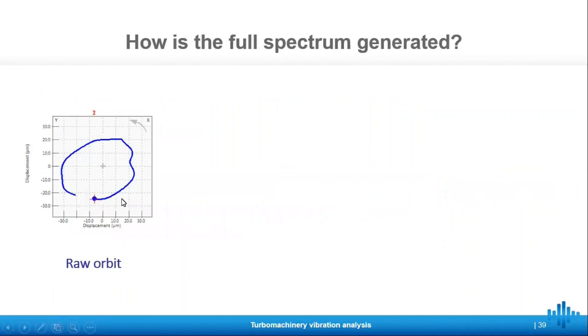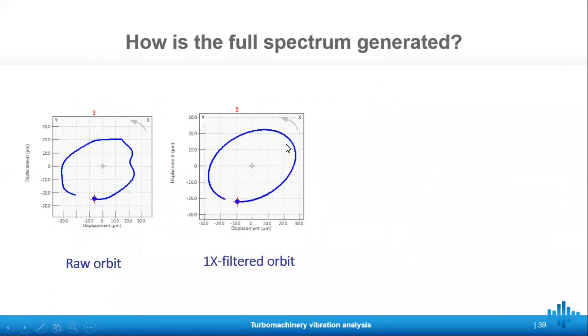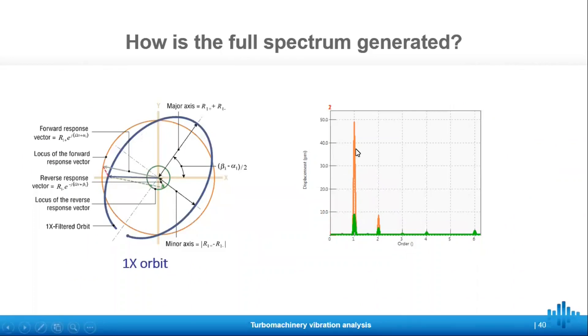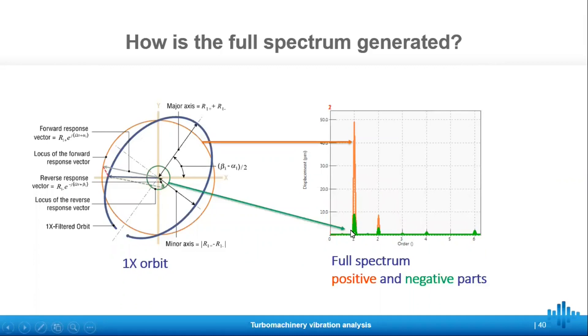Let's take a look at how the full spectrum is generated. We begin with the raw orbit shown on the left with all frequency content, and then the 1x filtered orbit is extracted from that. We then decompose that orbit into a circle — the gray vector minus the red vector corresponds to a green radius and an orange radius. The blue elliptical orbit is a sum of the positive orange circle plus the negative green circle. The orange circle will show in the spectrum with orange peaks and the green will also be overlaid in the same graph, so we can easily see the positive and negative parts of the orbit and at a glance get an understanding of how it is moving.